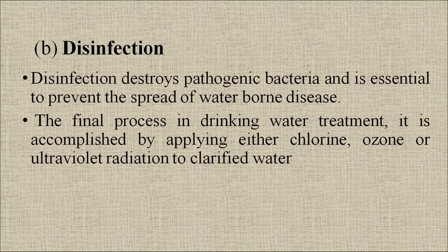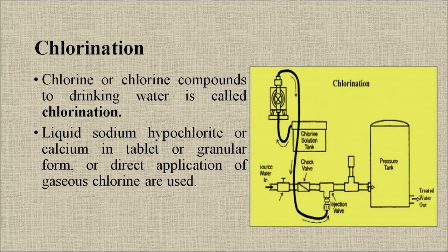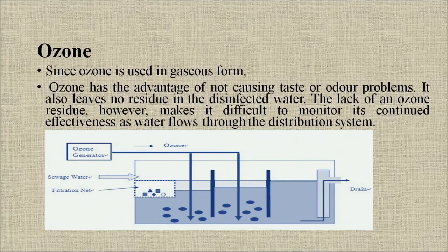Disinfection destroys pathogenic bacteria and is essential to prevent the spread of waterborne diseases. The final process in drinking water treatment is accomplished by applying either chlorine, ozone or ultraviolet radiation to clarified water. For chlorination, liquid sodium hypochlorite or calcium hypochlorite in tablet or granular form, or direct application of gaseous chlorine, are used. Since ozone is used in gaseous form, it has the advantage of not causing taste or odor problems and leaves no residue in the disinfected water. However, the lack of ozone residue makes it difficult to monitor its continued effectiveness as water flows through the distribution system.